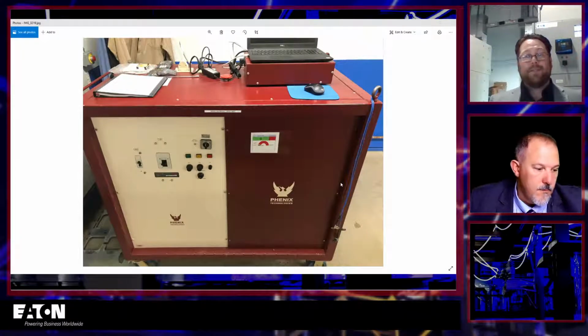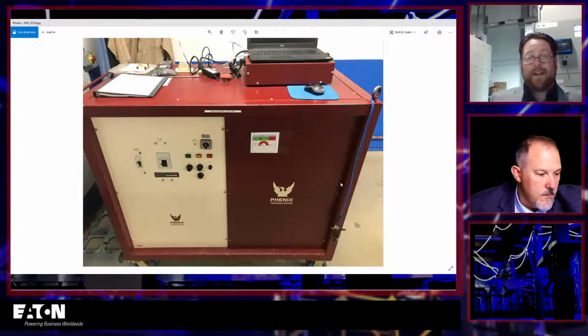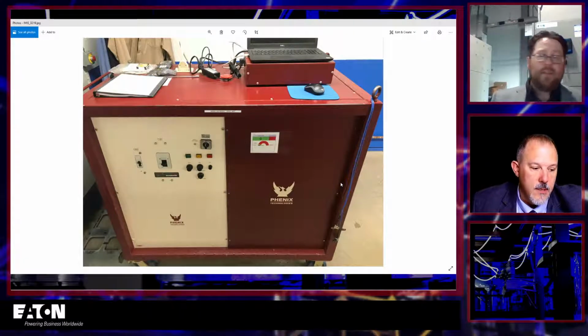Ultimately, that's when we switched over to secondary injection, and the thought process there is: how often does a CT or a sensor in a breaker fail? How often does the wiring on that circuit internal to the breaker fail? It's not common. It happens, but not real common. So we said, let's use these other injection test sets. They work really great ultimately, but they miss some of the testing.